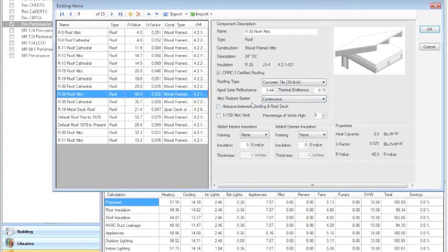Okay. Now, when you do the attic radiant barrier, other things you can consider doing on top of that. One is to increase the ventilation in the attic. So code requirement is that we have 1 in 300 attic vents. So that's 1 square foot per 300 square feet of attic. So we could consider doubling that to the 1 in 150. And that's going to supplement our attic radiant barrier by ventilating out all that heat that the radiant barrier is catching.